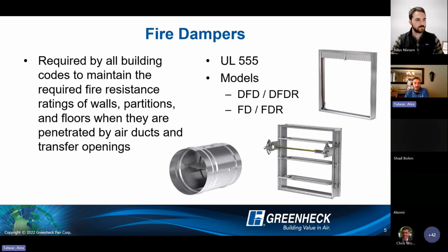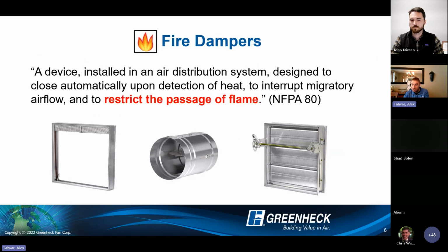First of all, fire dampers, their purpose being required by building codes. Essentially, they maintain the fire resistance rating of fire rated construction when it is penetrated by HVAC openings. They are tested to Underwriters Laboratories Standard UL 555. And for us, our models are DFD, the Dynamic Fire Damper group. The R at the end would be the round model, and then FD for Static Fire Damper, and FDR for the round static fire damper.